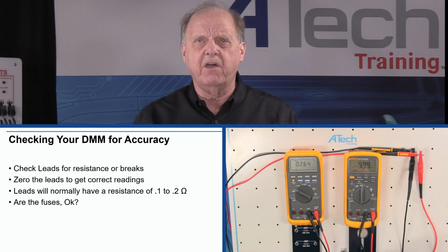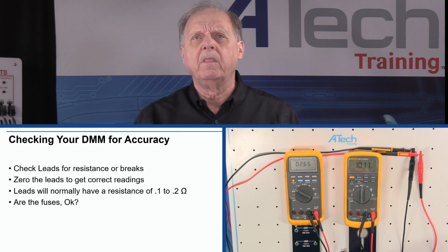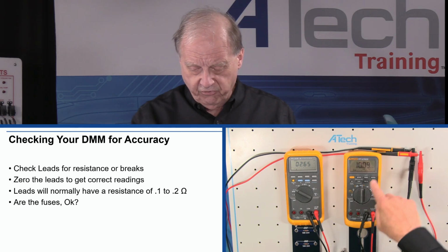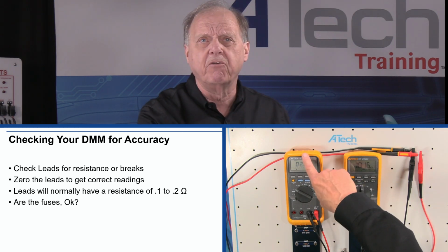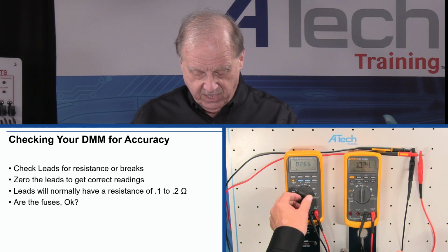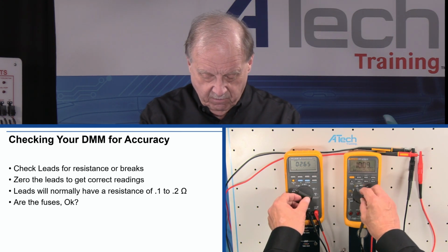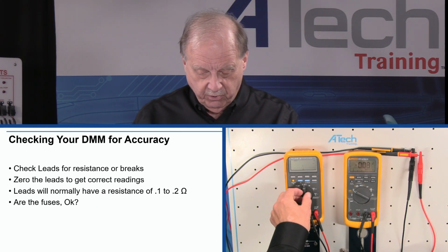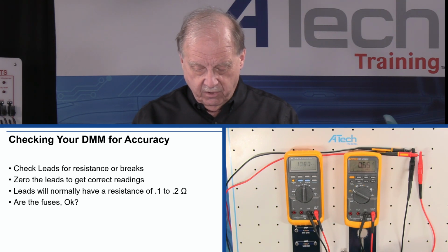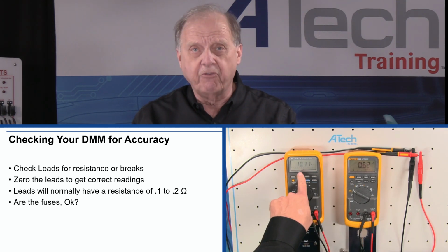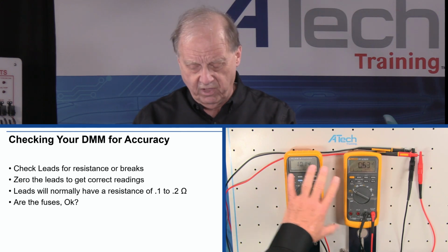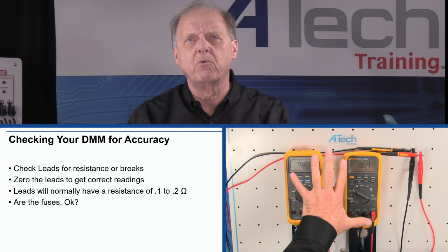But at the same time, notice what I've got at the top: 10 mega ohms. That means my impedance on this meter is 10 mega ohms. If I reverse it again, put voltage, put ohms, it doesn't read exactly, but it tells me on this meter I get 10 mega ohms. So I know these two meters are within reason.